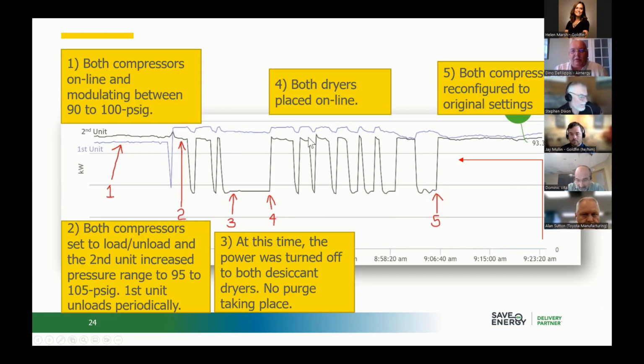Correct. So the 200 horsepower that was modulating was still pulling a good 120, 130 amps, but I wasn't getting a lot of air out of it. But again, it was the fact that we had two compressors set to exactly the same pressure, load, unload. One was modulating, one was fixed, I should say load, unload. And just by adjusting the pressure bands and the way they operated, I was able to load, unload one, and then obviously the purge. Mm-hmm. So those are the things you also have to look at when you're looking at energy reductions. How is the system working with all the ancillary equipment?